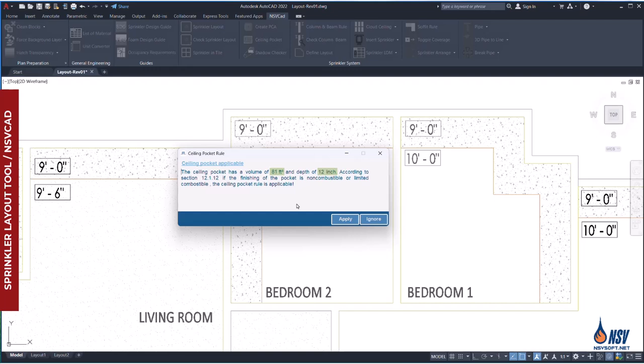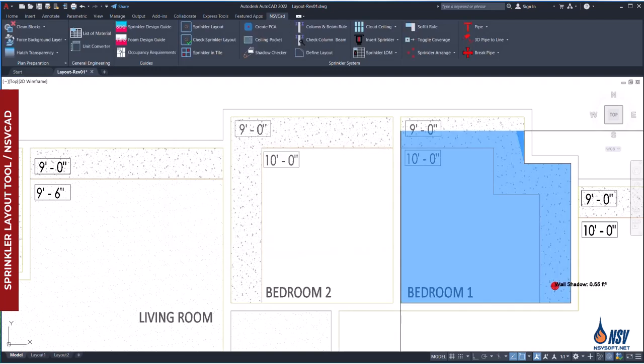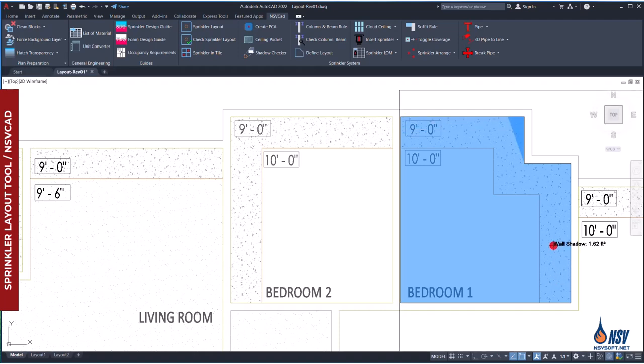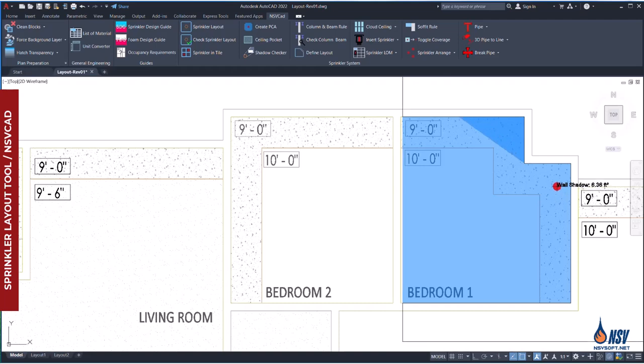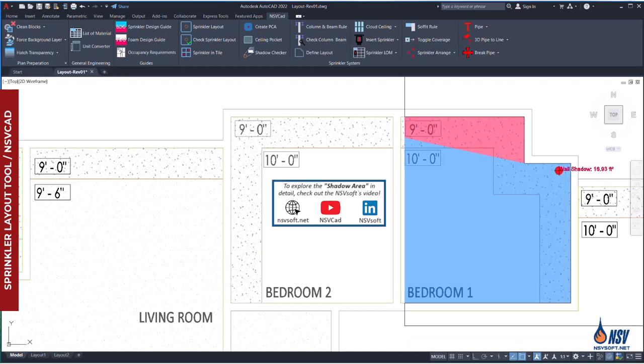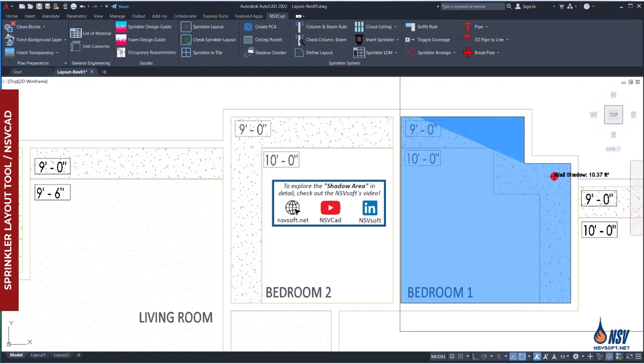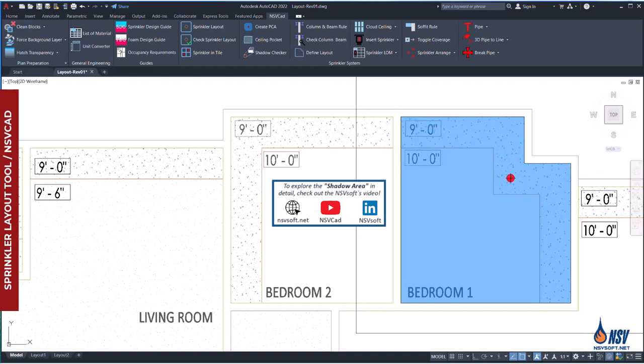Assuming the pocket has non-combustible finishes, we click Apply. The software then automatically places a pendant sprinkler beneath the soffit. Next, we adjust the sprinkler position to find an optimal location that ensures full coverage of the room. During this step, we must also ensure that no shadow areas exceed the maximum allowable limits specified by NFPA 13.